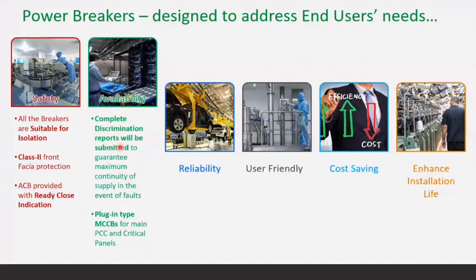So total discrimination should be maintained from ACB incomer, ACB outgoing, ACB incomer, MCCB outgoing, MCCB incomer, MCCB outgoing, MCCB incomer, MCB outgoing, and MCB incomer, MCB outgoing.